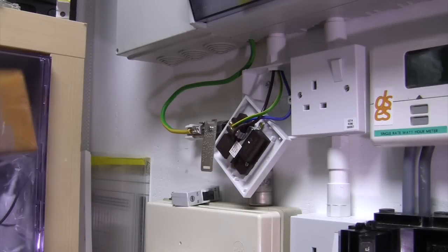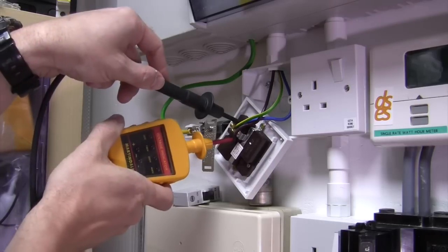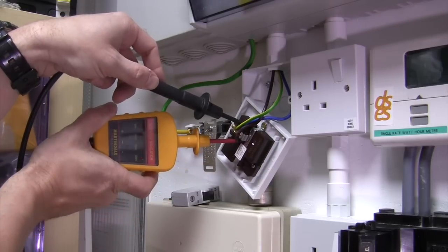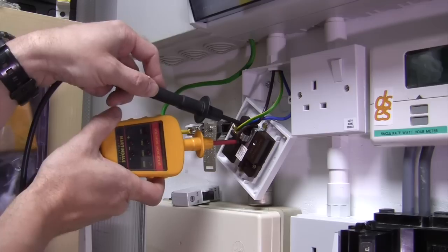So now I'm behind the socket at the point of the circuit I actually want to be working on, and I'm pretty confident the circuit is safe and locked off, but I'm not going to make any assumptions. So I'm going to use my voltage indicator to check between line and neutral, and sure enough I'm getting no lights there. It's indicating that it's dead.